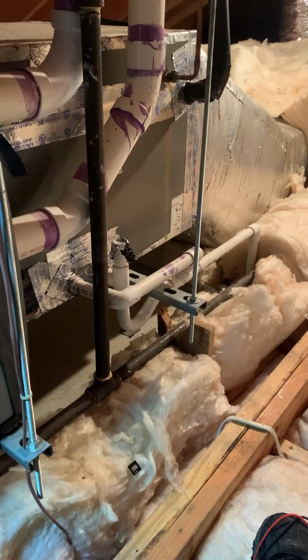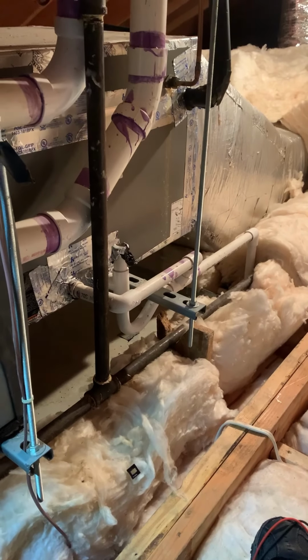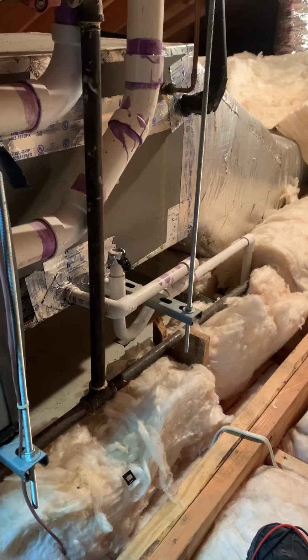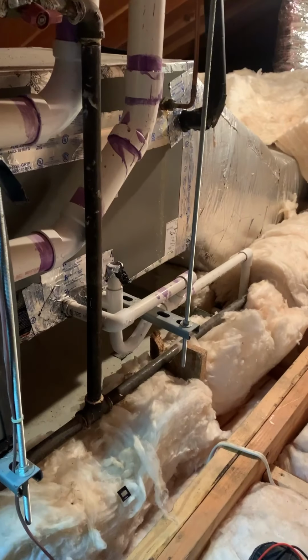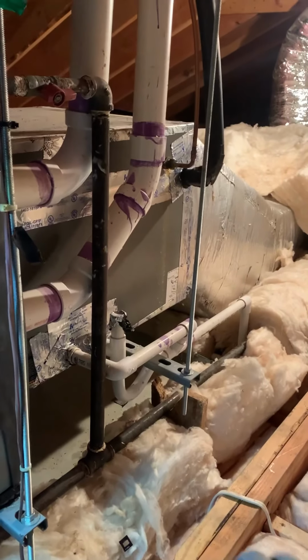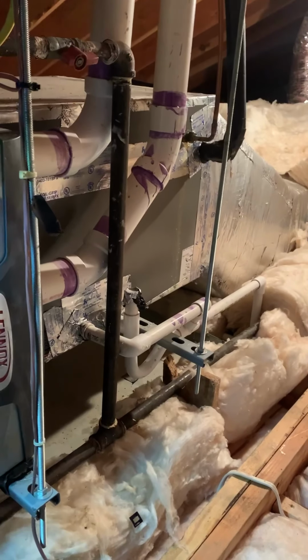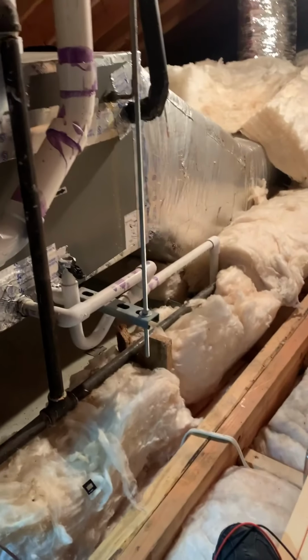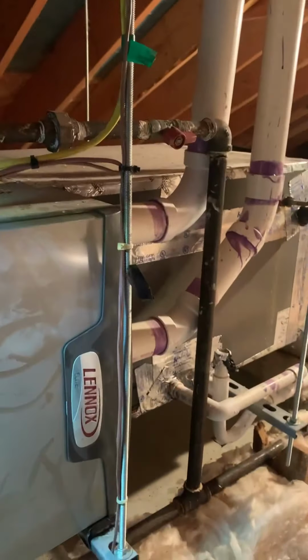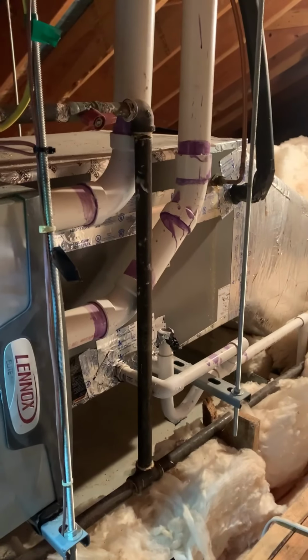If the coil is before the blower, right next to the return duct, and that's sucking air to go through the coil, and then you have the blower afterwards, that would be negative pressure, and you do need that trap. All right, guys. So we got less than 1 amp on this machine over here for the load. It should not pop this transformer.